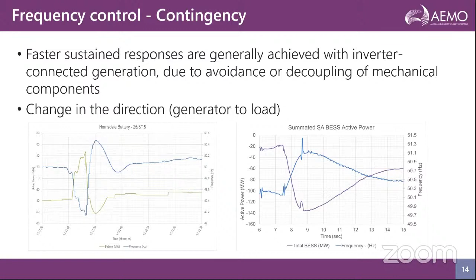Just one more slide on the fast frequency control. And this is another way to show how batteries responded during the same event. I'm attempting to show the fast frequency response capability of batteries here by reversing the secondary y-axis. So just pay attention, right? The blue trace is for frequency on the left side of the figure. So when you see the blue trace going up, in fact, the frequency is going down. Have a look at the secondary y-axis, how it is reversed on both slides. So a key message here is how the megawatt response from the battery is following frequency very closely. There is a delay, but it's very small. A sub-second response is well within the capability of batteries.